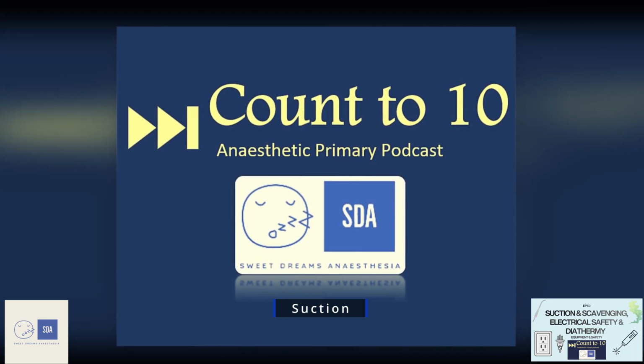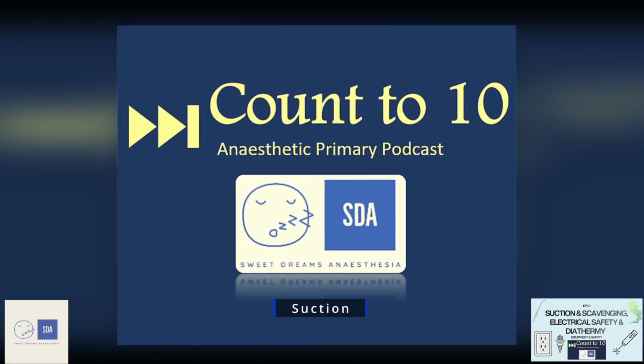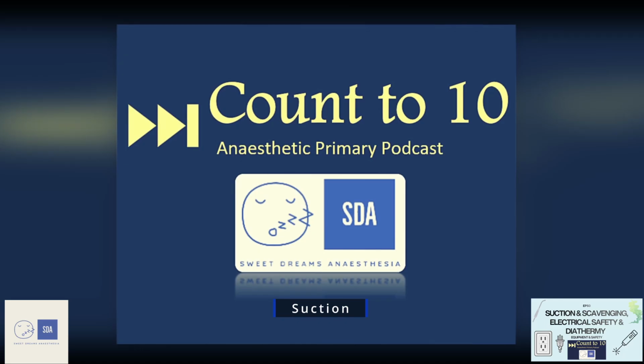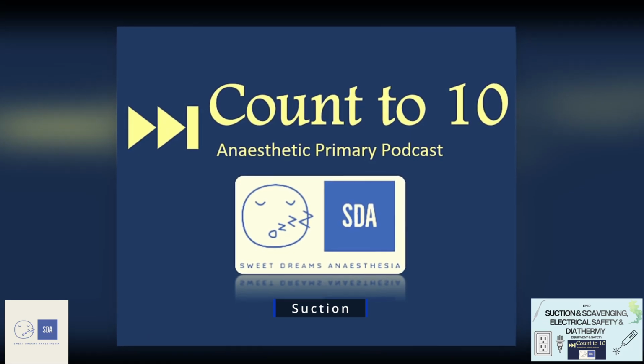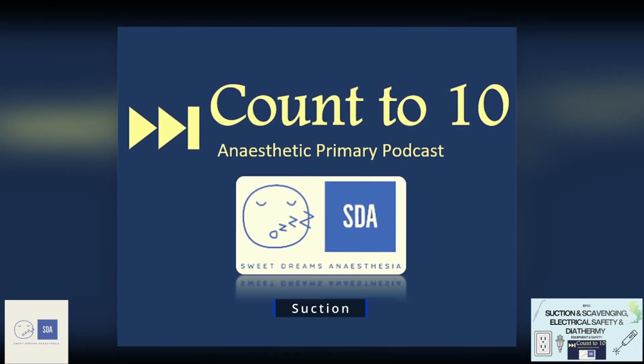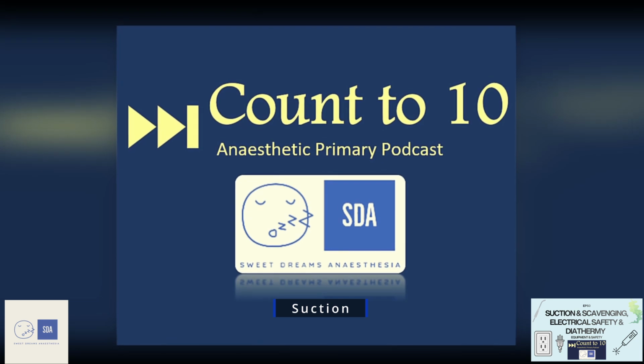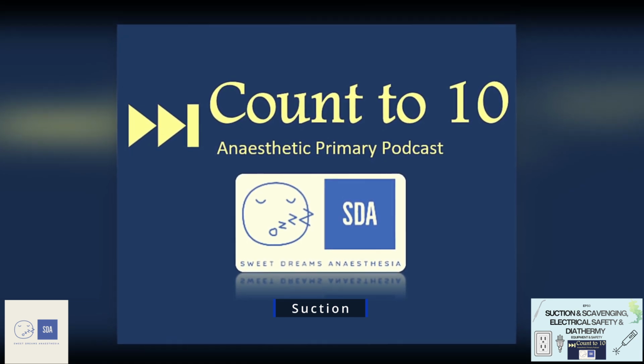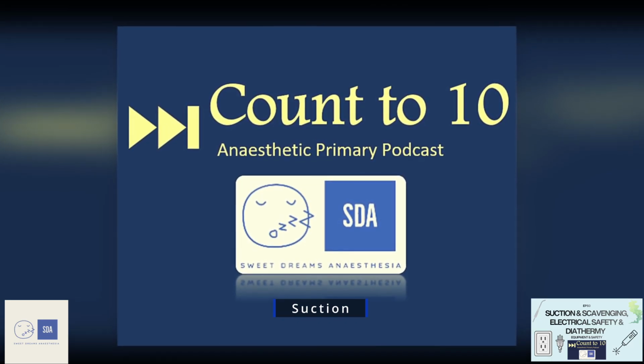Here on the wall you can see the suction outlets, and these are connected to the main facility vacuum device that's probably located somewhere in the dungeon of your hospital. There are many types of electrically powered mechanical pumps, and you don't have to know the exact names of each, but it's most likely going to be a rotary vane pump. Regardless of the type, the principle of the vacuum is the same. For a long time, I used to think that suction worked by generating enough power to pull things into the reservoir or the disposable can. But that's the wrong way to think about it.